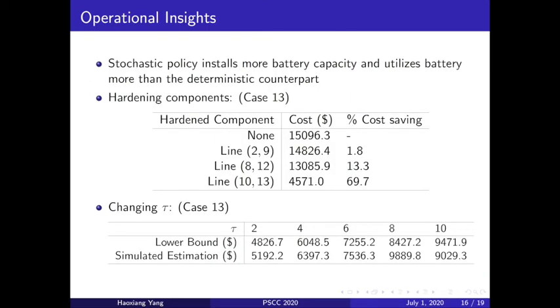We also want to do some sensitivity analysis here. We want to see how much we want to afford to harden some lines to exclude itself from disruption, or how much impact you can create by changing the recovery time. Here we can see for different lines, hardening them means excluding them from the possibility of disruption, and they yield significantly various cost savings. For this example, line 1013 is quite important and it will yield a large percentage cost saving. For the decision maker, it tells them that it's more beneficial to harden such lines that yield larger cost savings. A general trend for the recovery time is, the longer the recovery time, the cost is going to be larger. Which means that it's better to fix the components in the power system quickly.